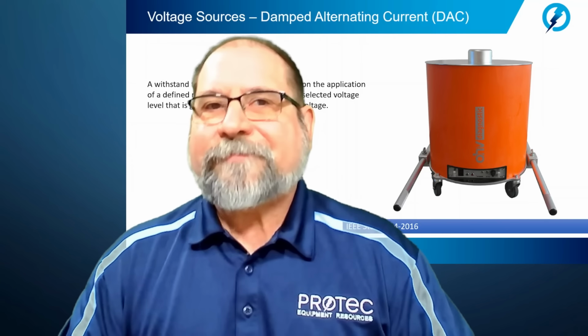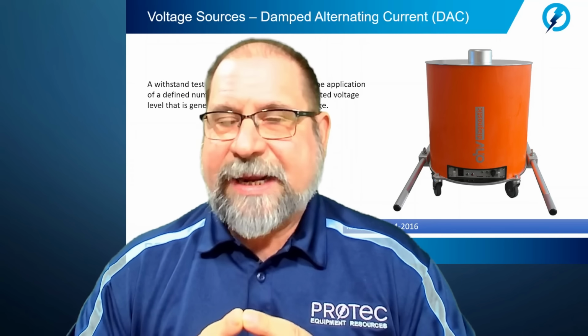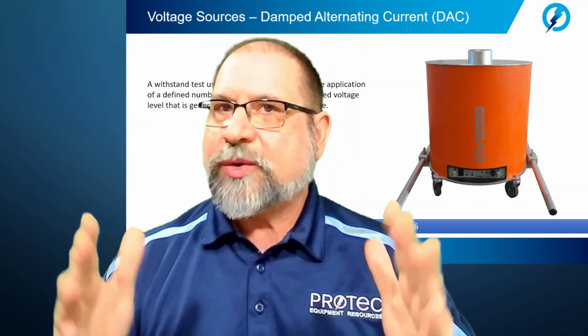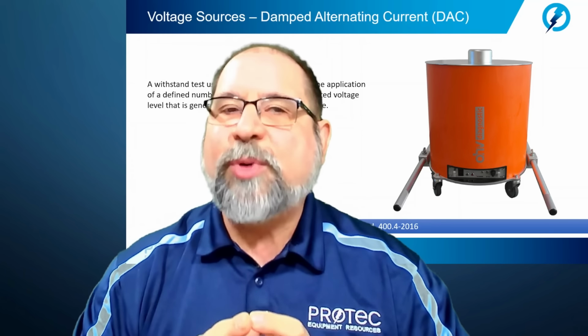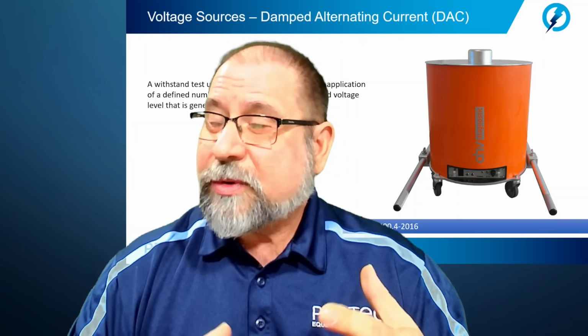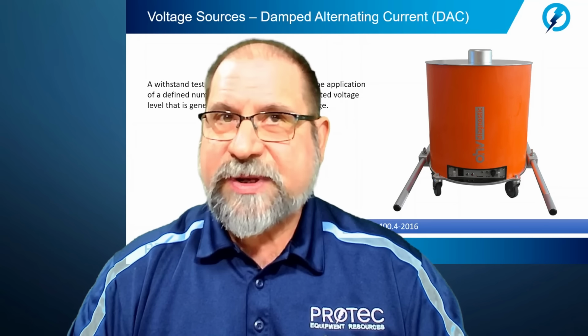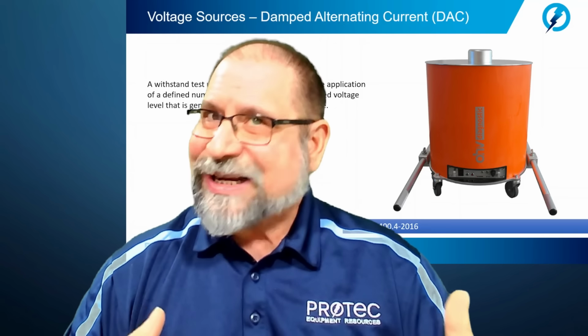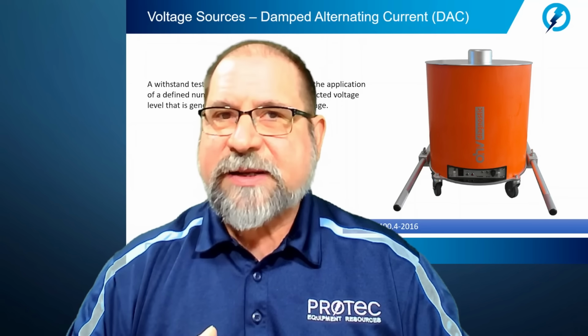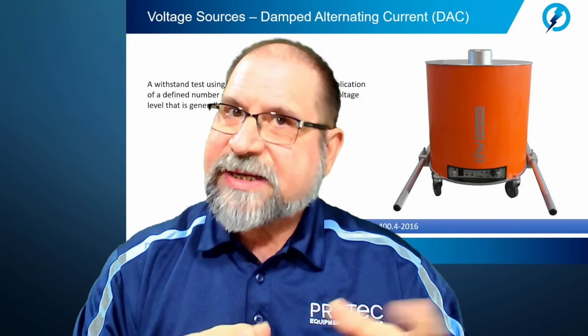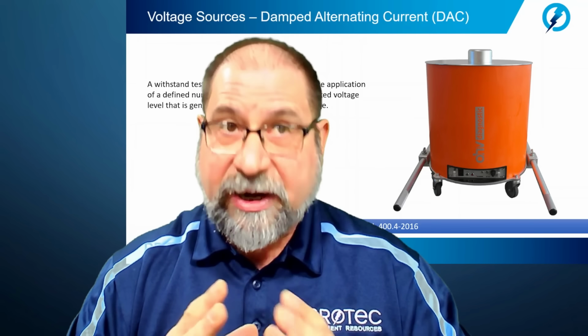Now, when we look at the DAC, this is kind of a short duration pulsed output. So in order to conduct a high potential withstand test, as we stated, this is based upon a number of excitations, or a number of pulsing actions, into the cable specimen under test. Now, this is brought out and discussed in IEEE 400.4.